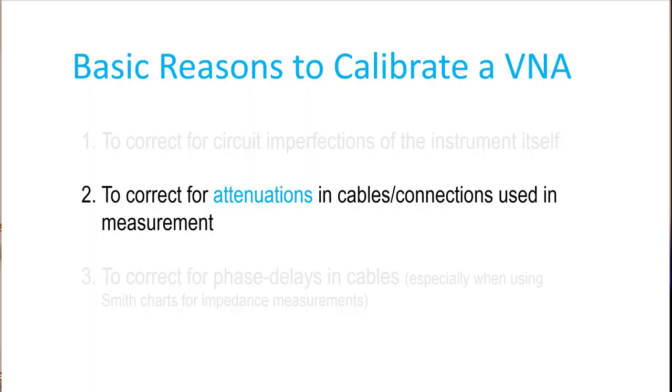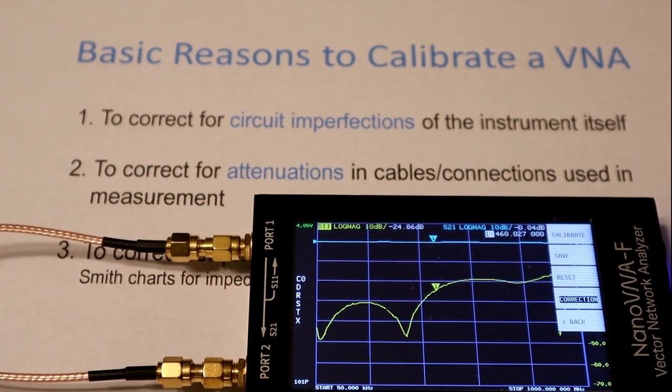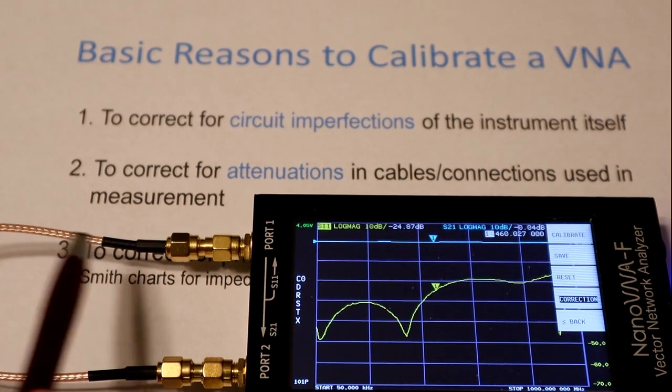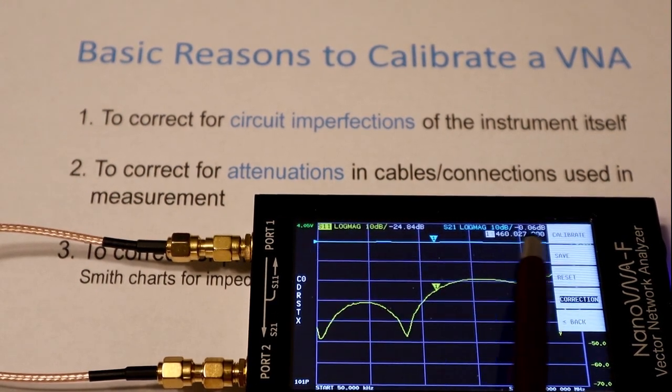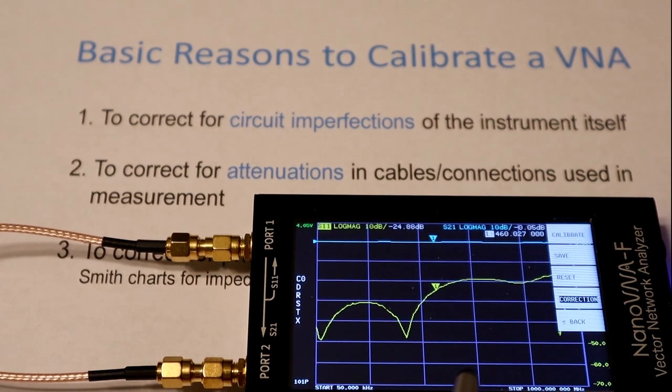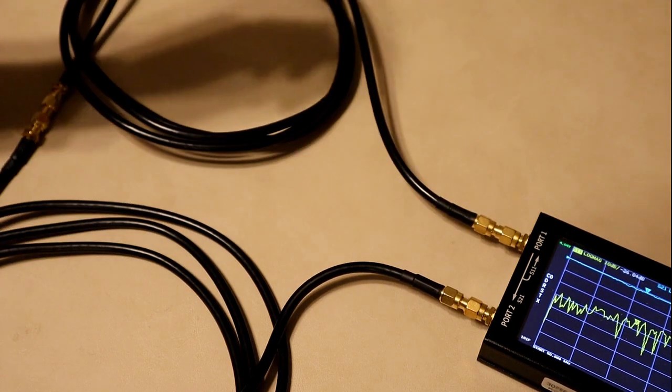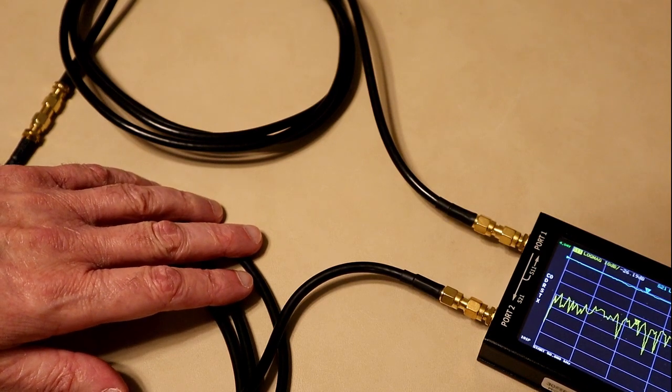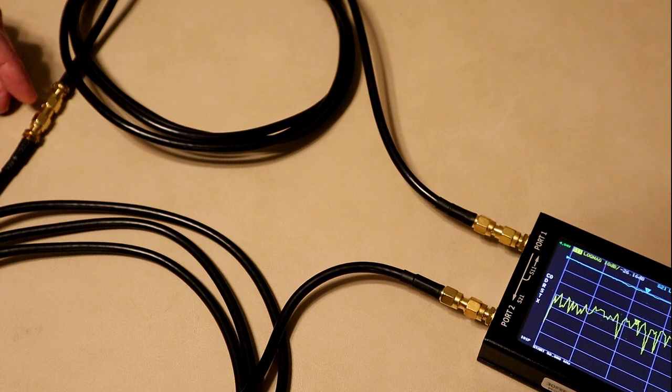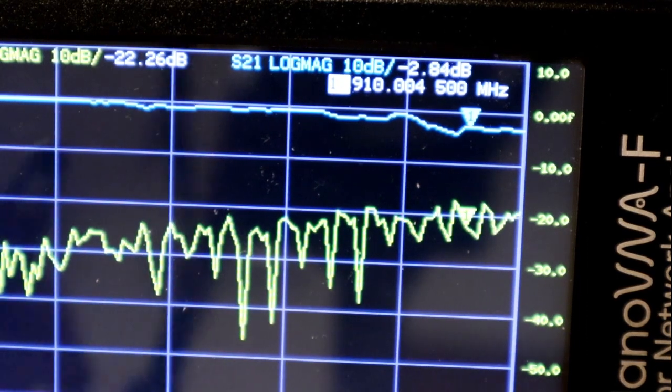To demonstrate when you might need to do CAL for number 2, to correct for attenuations in cables and connections used in the measurement, I have this setup with port 1 connected to port 2 using the cable I used during the calibration. And we have a nice blue line here at 0 dB across frequency from 50 kHz out to 1 GHz. Correction, I've turned back on. But suppose the device we want to measure is not such that we can put it right at the VNA.